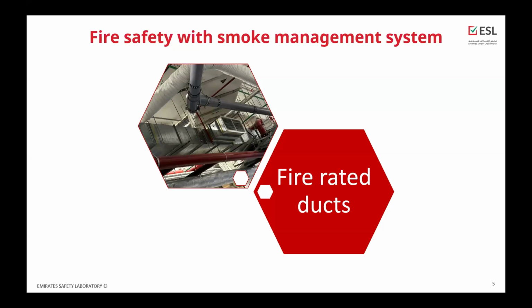The second is extraction of the smoke. The fire-rated smoke extraction ducts are designed to actively remove smoke from the fire-affected areas, reducing the risk of smoke inhalation, as well as improving visibility and the process of evacuation. This is also very important for the firefighters' teams, to facilitate their actions and increase the safety of their job. When we are designing the building and the smoke management system, our first focus in terms of fire safety is to make the evacuation process faster and safer for the occupants. But we cannot not focus on the safety of firefighters and what happens after the evacuation. So post-evacuation actions are also very important.